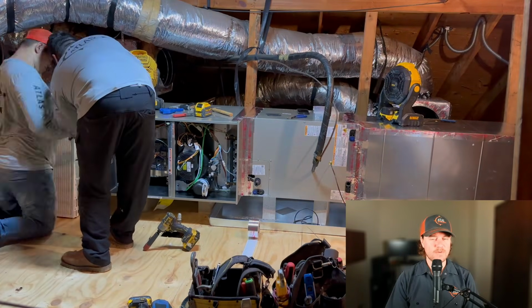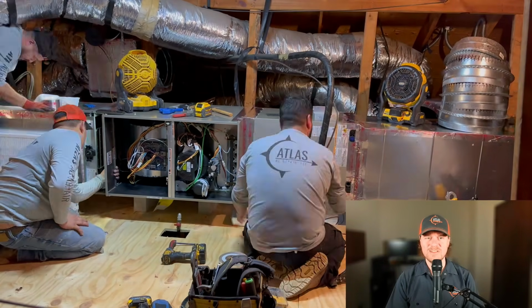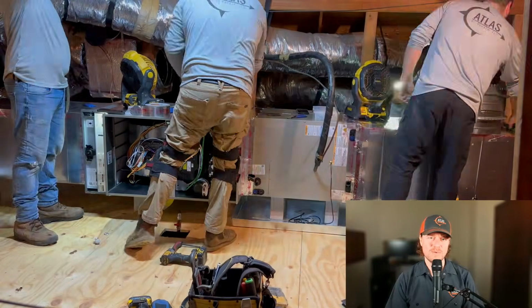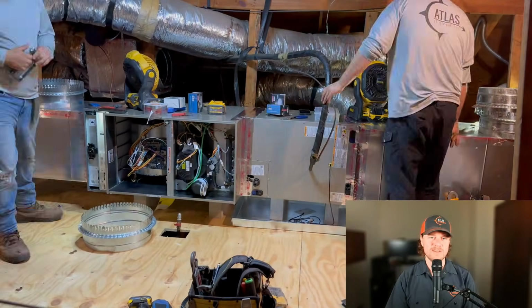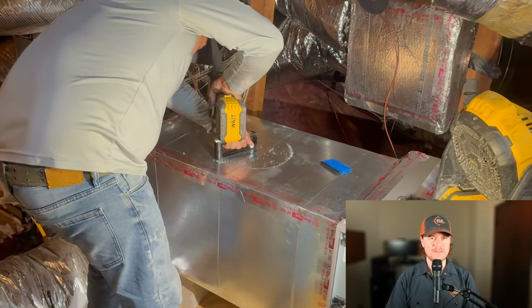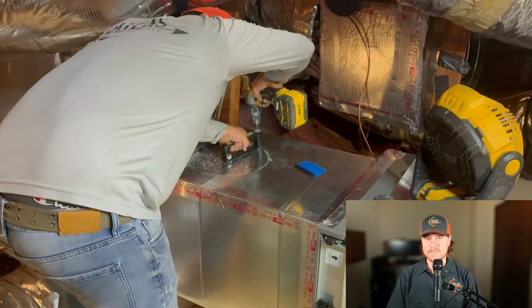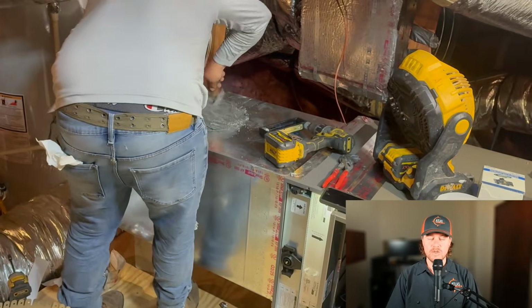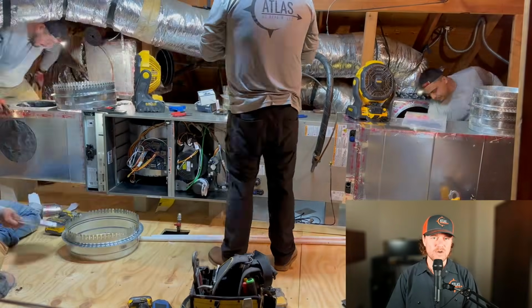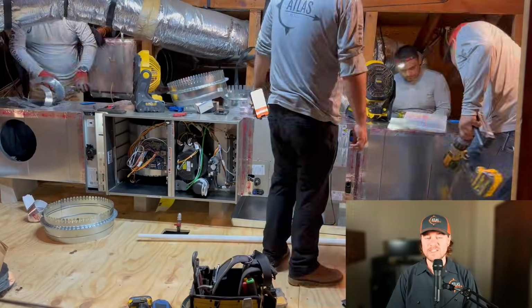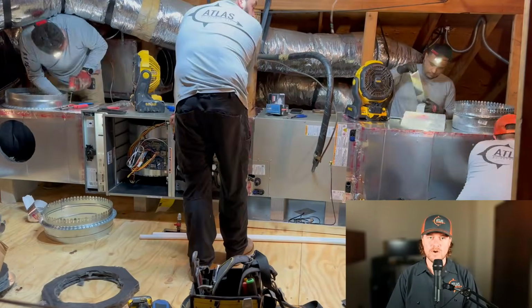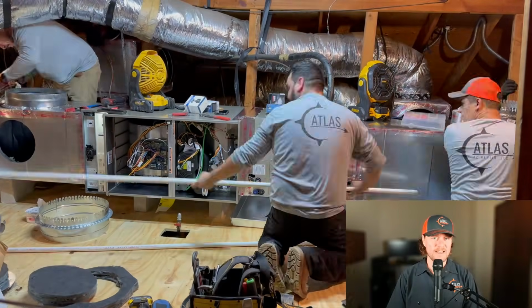And the next thing many folks like about it is energy savings. Because if you have unoccupied spaces for long periods of time, why spend the money to condition that space at the same rate as the rest of the house? You can simply throttle back the system in those areas until those spaces are needed. Overall, with this system, you end up with a high degree of temperature control in multiple spaces throughout your house. And since the system can ramp down to 20%, you get the highest level of comfort that a ducted zoning system can provide, along with additional energy savings because you no longer have to overheat or overcool spaces that don't need it.